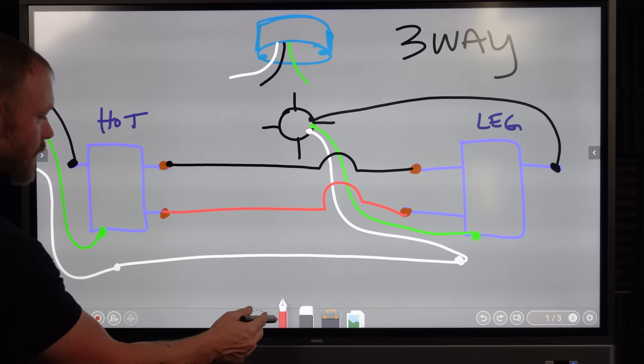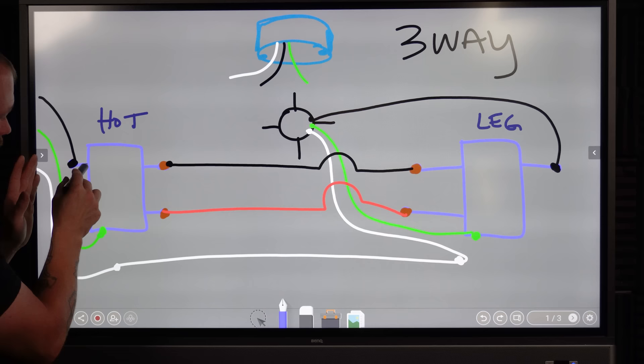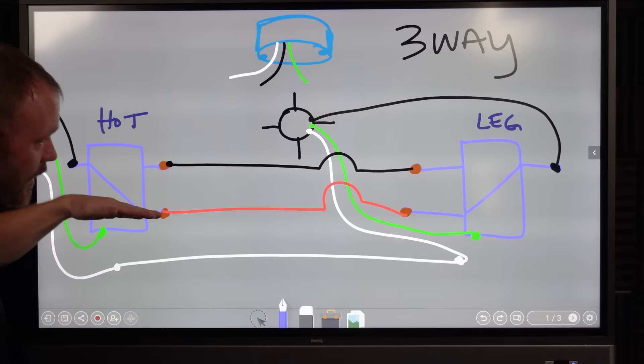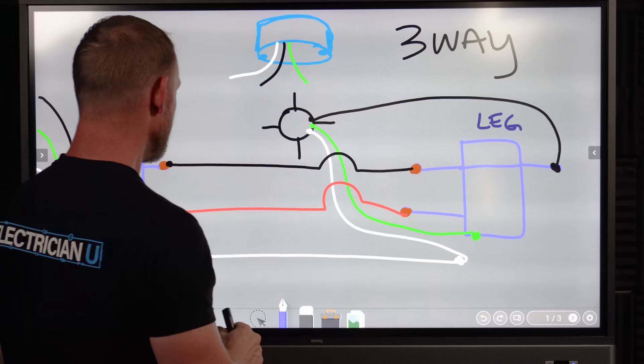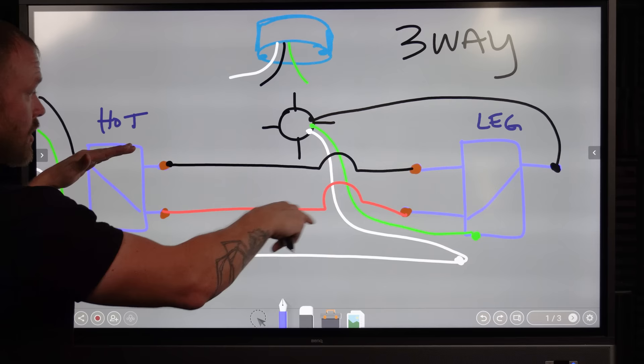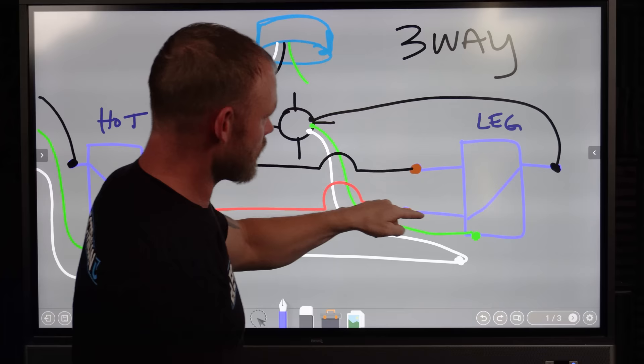The red — our other traveler — goes straight across and hooks to the other switch. So you've got traveler screw to traveler screw on both sides. Your black screw on the leg side goes up to the light, and the black on the hot side hooks to the incoming power. Inside the switch there's what's called a common, because it has something in common regardless which path it's taking. When you flip the switch in one position, the flapper goes down and allows current through; flip it the other way and it connects on the other side, breaking the circuit and turning the light off.